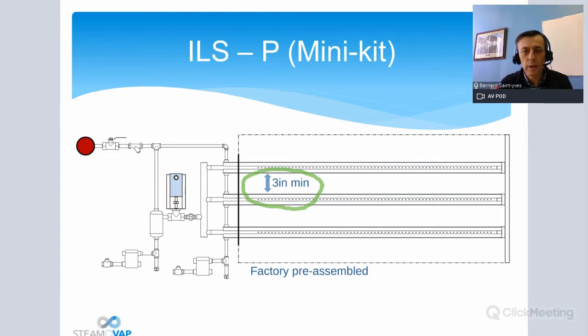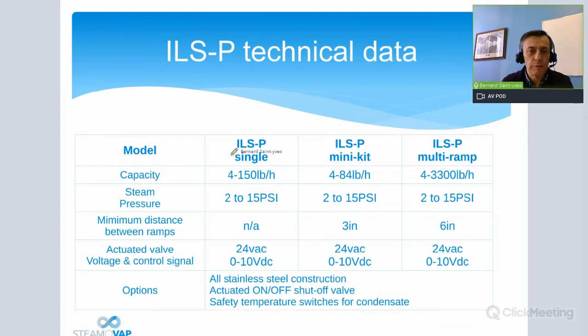Okay. So let's look at the different capacities for this method. I would say the jacketed steam humidifier called ILSP at SteamOVAP. So for a single ramp, the limitation will be the duct dimension. Okay, we put 150 pounds, but you have a certain capacity per nozzle and the distance between the nozzles, so that's a limitation. Okay. Then the mini kit, again, the same thing. You have a certain limitation in the construction. Okay, so we have limited it to 84 pounds an hour. But the multi-ramp, you can go to whatever capacity you want. 3,000, it's not a problem.